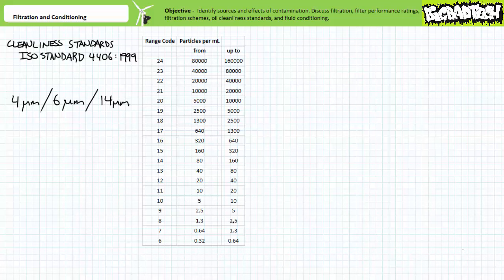Moving on, oil employed in a hydraulic system has formal cleanliness standards established by the International Standards Organization. For applications necessitating extreme cleanliness, it makes sense to start with the cleanest oil available, whereas those applications not necessitating extreme cleanliness can get by with a cheaper, less clean oil. Hydraulic oil ISO cleanliness standards are communicated using a three number code, sometimes two, where each number in the code represents a range of particles of a given size per unit volume. These three numbers respectively represent particles greater than 4 microns, but less than 6 microns, particles greater than 6 microns, but less than 14 microns, and finally particles greater than or equal to 14 microns. Each number represents a range of permissible particles of a given size per unit volume.